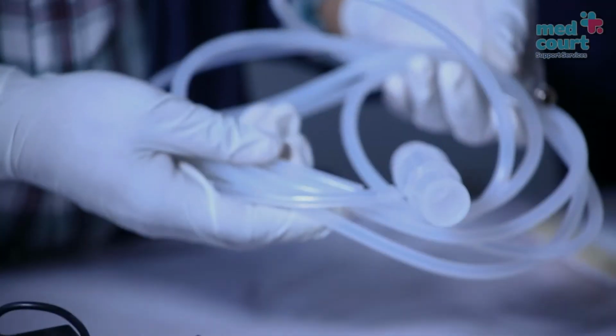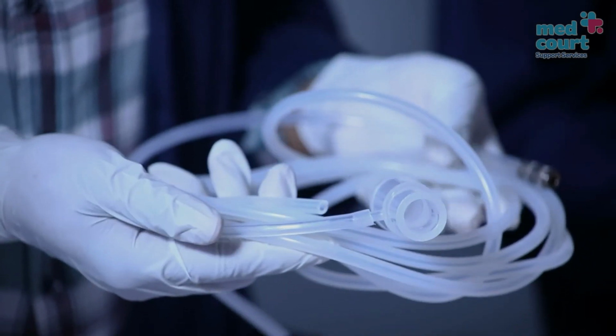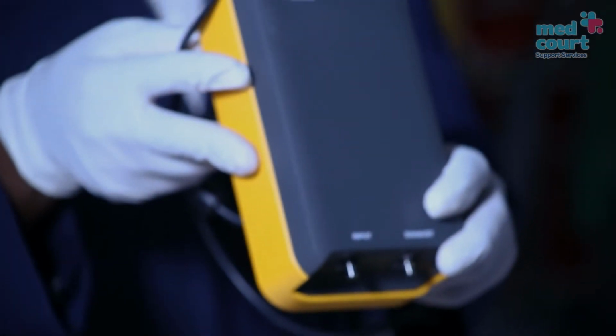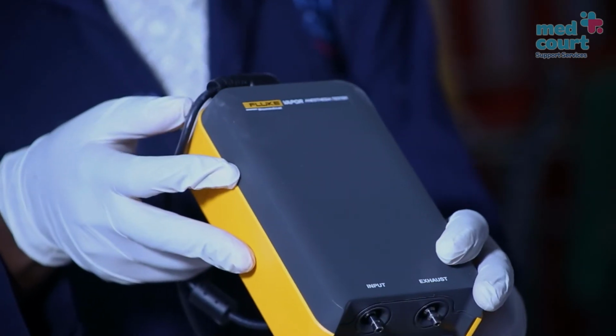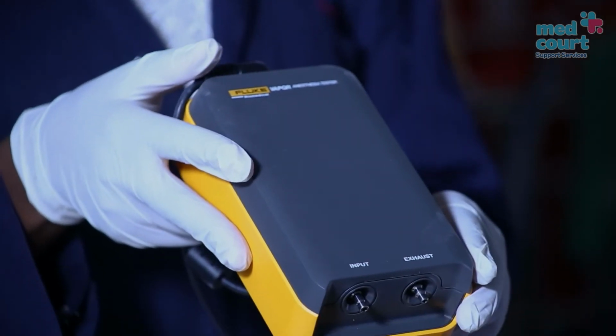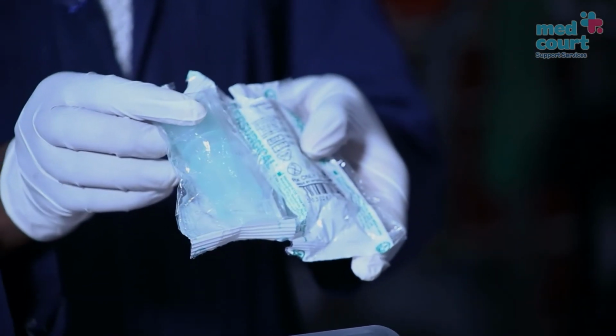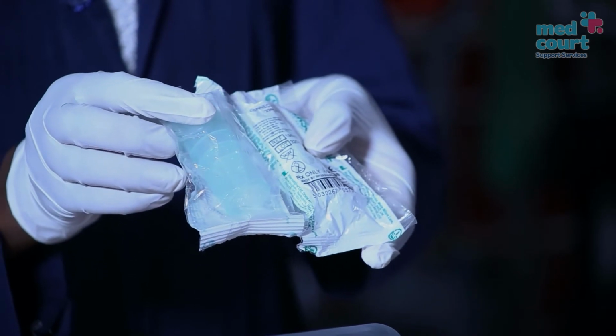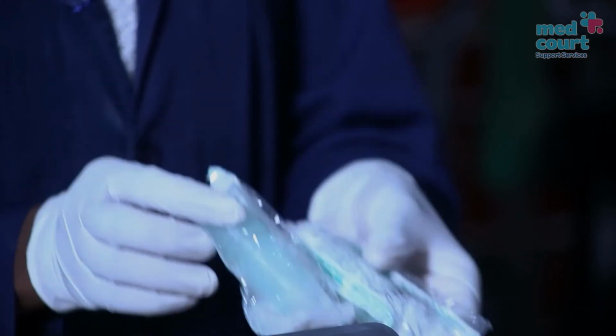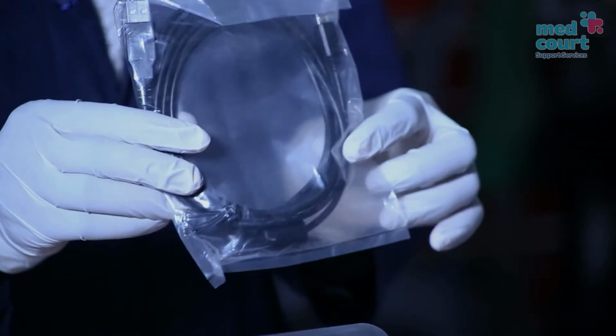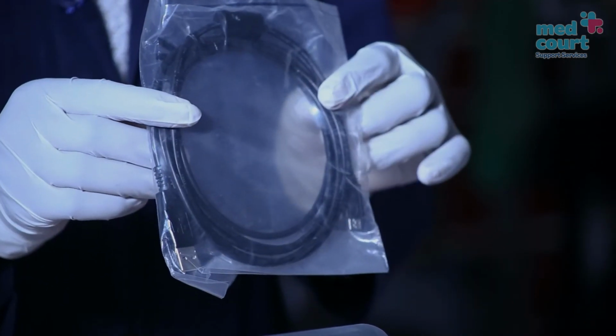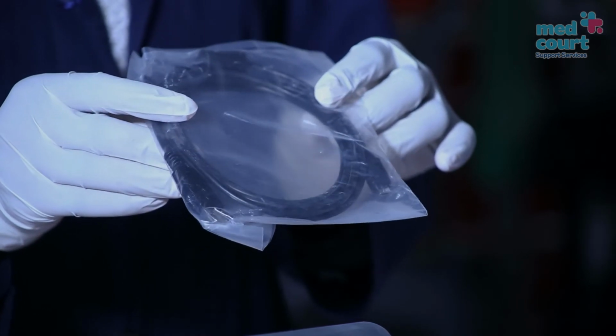We have the 1.2-meter silicone hose, which is used in addition to the anesthesia tester as an accessory. We also have the anesthesia tester, which is used to test for gases from the vaporizer when testing the anesthesia machine. We have the connectors, which are also connected to the Y-piece of the gas flow equipment and connected to the VT900A as well. We have the USB cable, which can be used to connect to the VT900A and whatever device is used to extract test information from the VT900A.